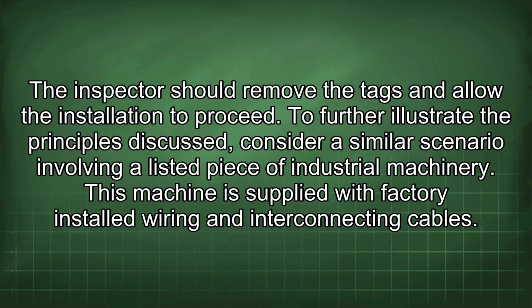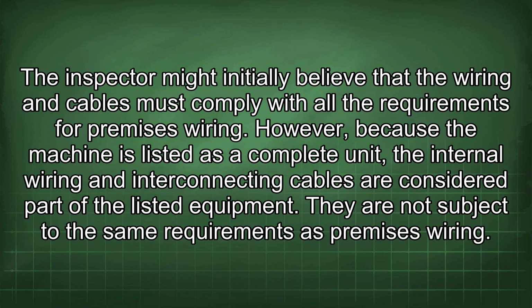To further illustrate the principles discussed, consider a similar scenario involving a listed piece of industrial machinery. This machine is supplied with factory-installed wiring and interconnecting cables. The inspector might initially believe that the wiring and cables must comply with all the requirements for premises wiring. However, because the machine is listed as a complete unit, the internal wiring and interconnecting cables are considered part of the listed equipment. They are not subject to the same requirements as premises wiring.